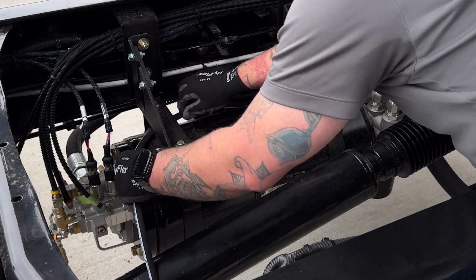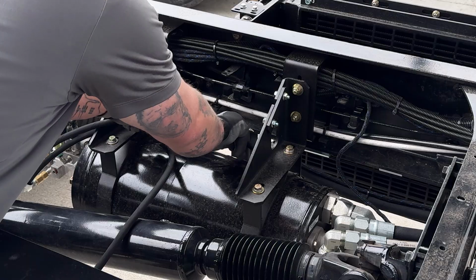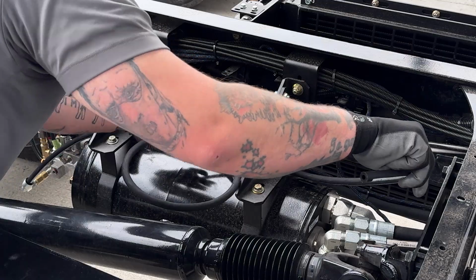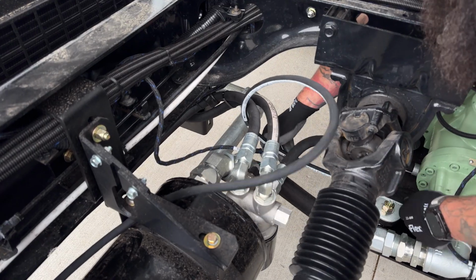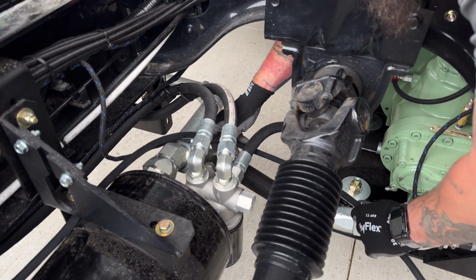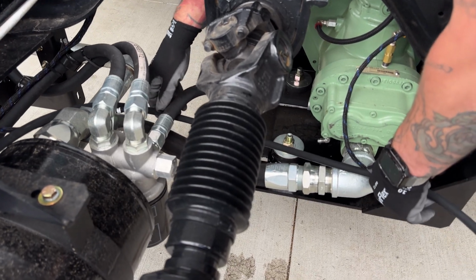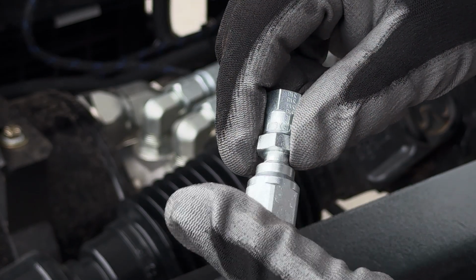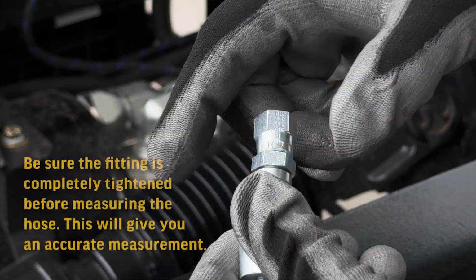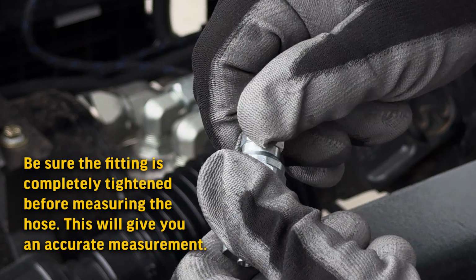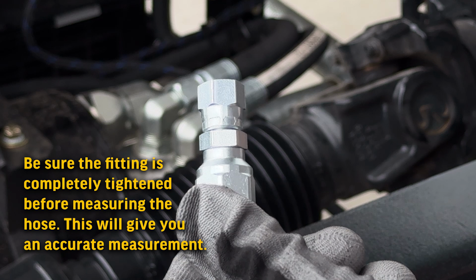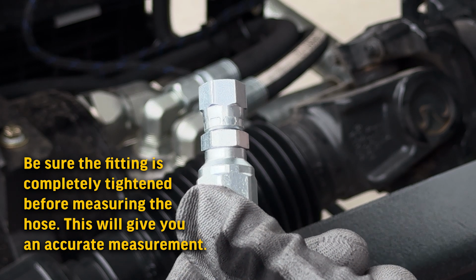Route the scavenge line hose to the air end, ensuring it does not come into contact with any surfaces that could cause abrasion or wear. Your 1/4 inch hose should come with reusable fittings. Be sure the fitting is completely tightened before measuring the hose. This will give you an accurate measurement.